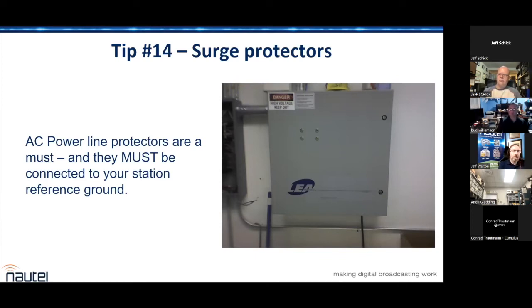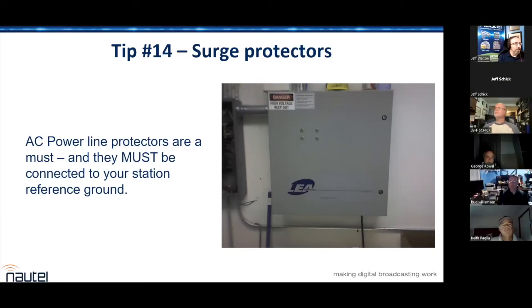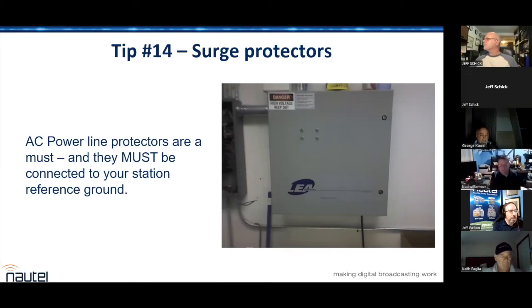Here's something to remember from 10-15 years ago: it wasn't part of the NEC, and a lot of older electrical inspectors struggled against it. Your station ground, your AC, your RF ground, what the coax cable is grounded to, the transmitter, and everything else, needs to be connected to the power company's AC ground. If they're not physically tied together, you've got an impedance between the two, and you don't know if your surge protector is going to do you any good or not.